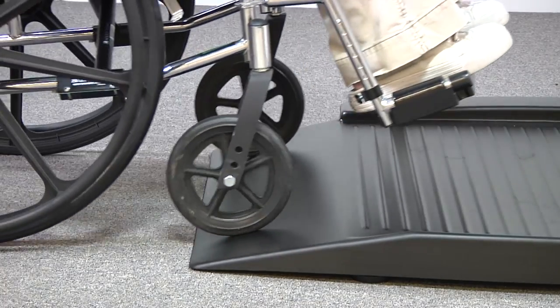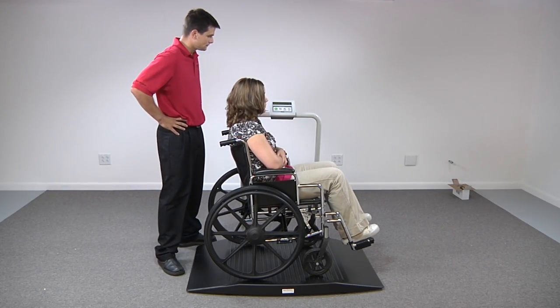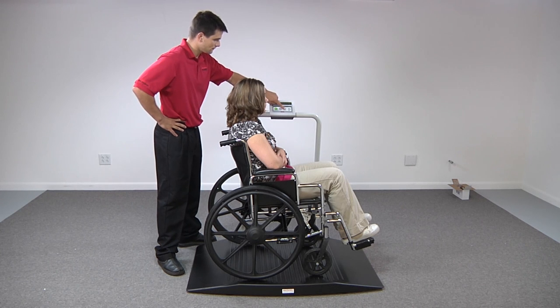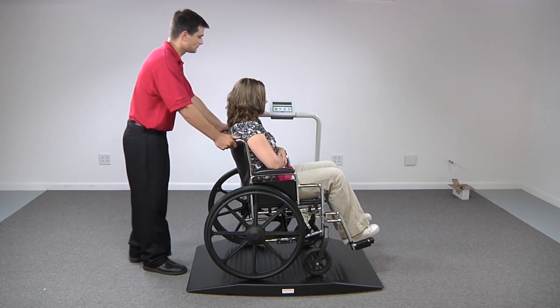Begin to weigh your patient as normal, and the scale will display the actual weight of the patient. Once the patient has stabilized, confirm the weight using the re-weigh key. You may continue to use the same tare weight for multiple patients as long as the same wheelchair and equipment is used.